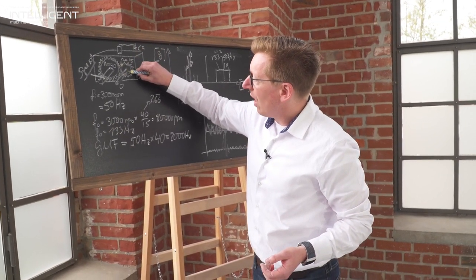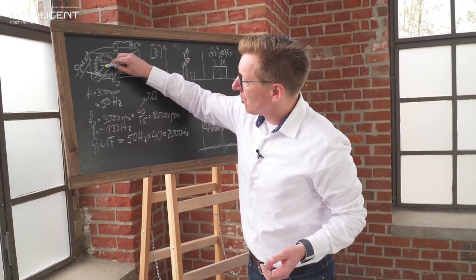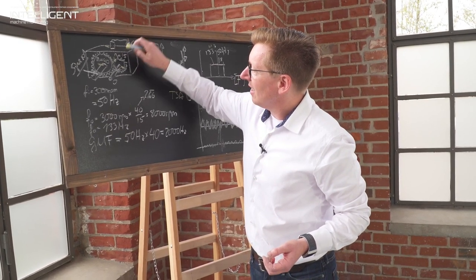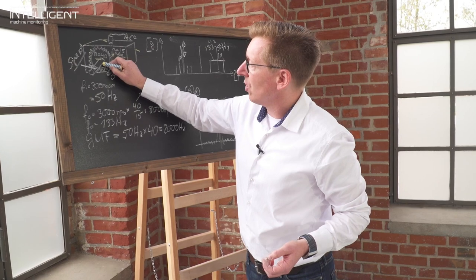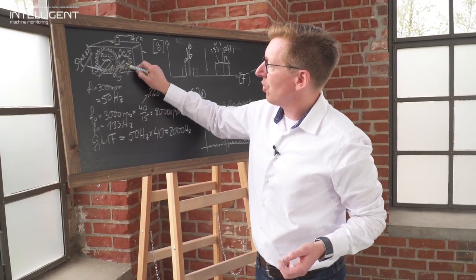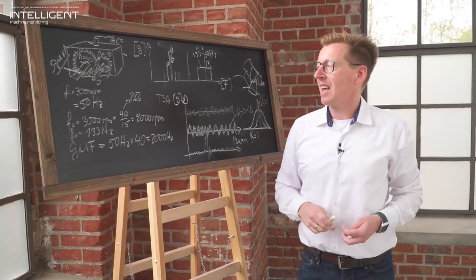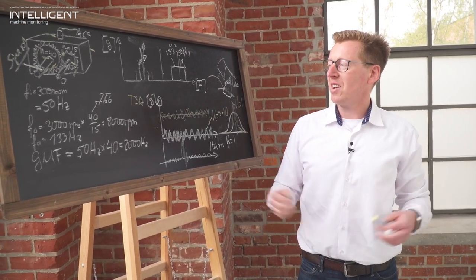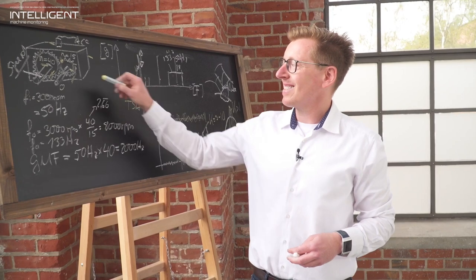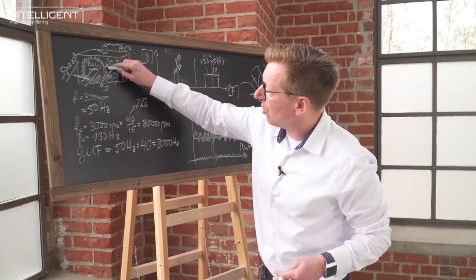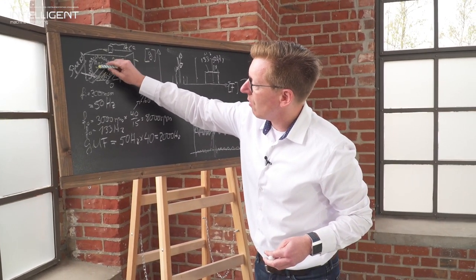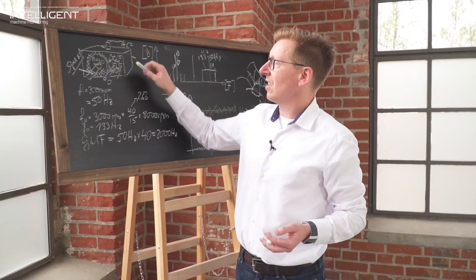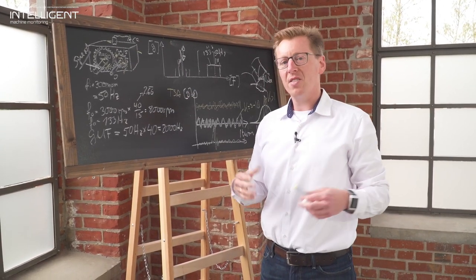Yeah, as a rule of thumb it'd be really advisable on a larger gearbox to have each shaft equipped with at least one radial sensor on either side, so this will be on either side of the gearbox, and one axial sensor per each shaft.